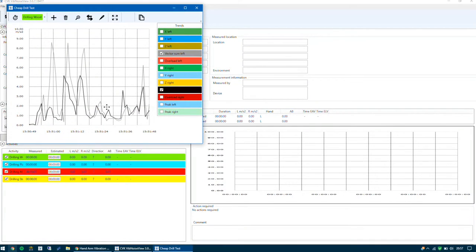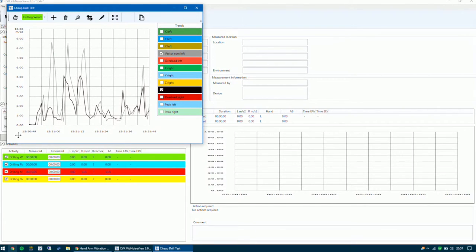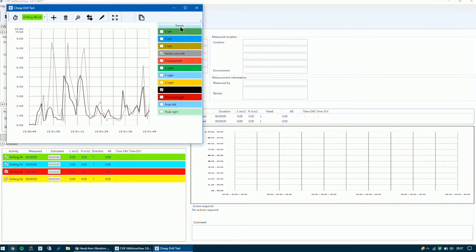What we want to do is view the graph of this measurement. When I click that icon a new window appears where we can see the level — the measured metres per second squared value — on the vertical axis, and on the horizontal axis we have the time which is increasing. On the far right hand side we have the trends, which are our vector sums and our X, Y, Z values.